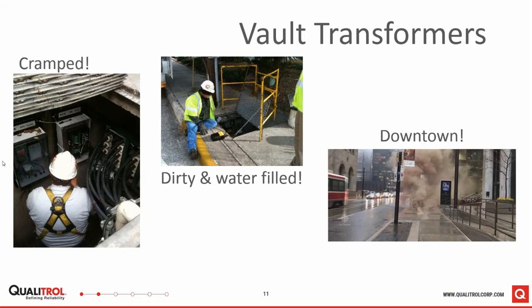And in addition to the public safety, we also want to ensure the safety of our employees that are working down in those vaults. And having remote indication of the health of the transformers is very important. I've actually talked to some smaller utilities that have vaults that have said they've never had a vault transformer failure. And so when I ask them how old is their fleet and how long they expect these transformers to really last, they say, well, our fleet is 20 to 30 years old and we don't know how long they're going to last.